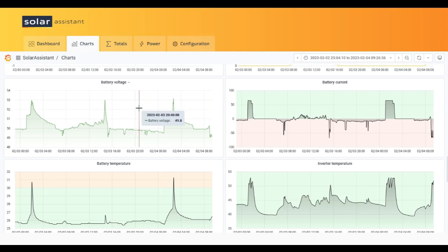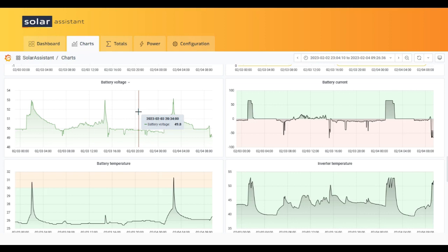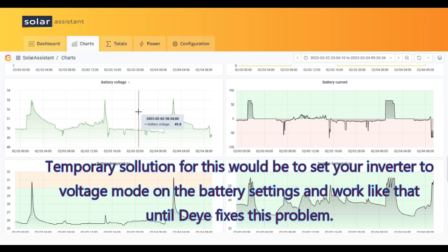So if you have a Deye inverter connected with Pylontech through BMS, just watch out for your batteries. For now, the solution is to set the battery to voltage mode and then it will work properly.